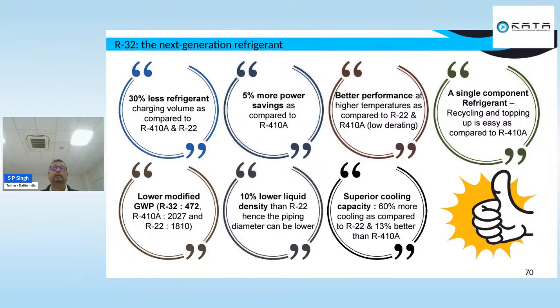We are saying if a certain amount of refrigerant charge has to be carried out, then 20 grams per meter has to be charged. But company to company, manufacturer to manufacturer, it is different. As we increase the length of our tubing copper pipe, we have to increase the amount of refrigerant, otherwise it won't give the performance we should get.